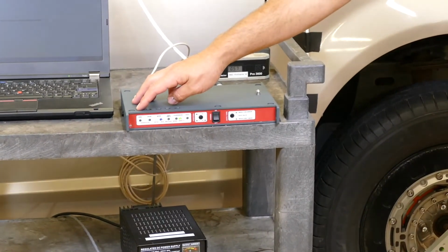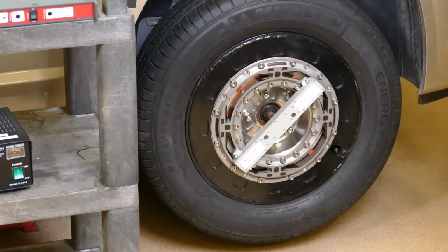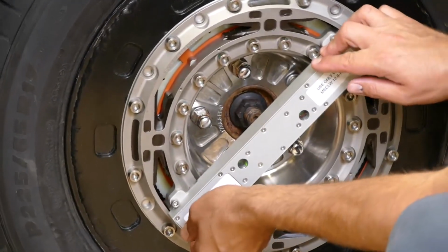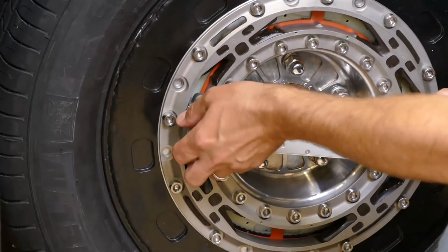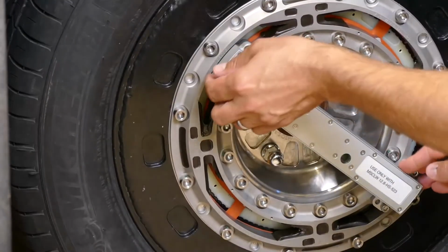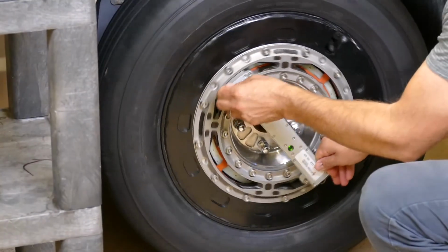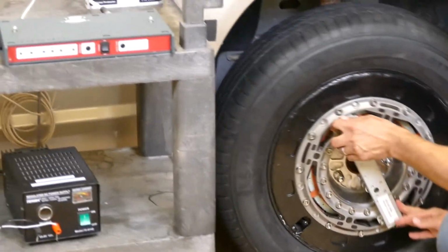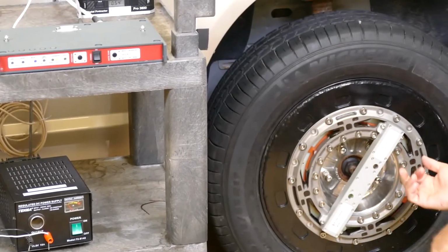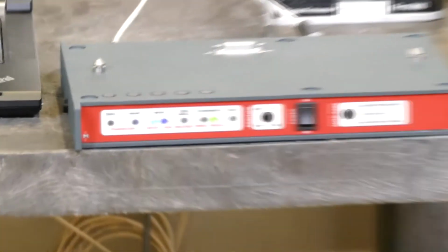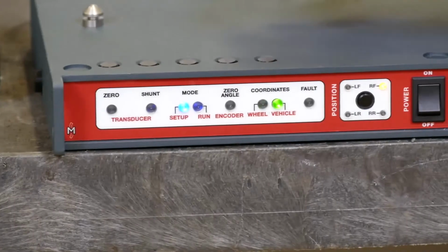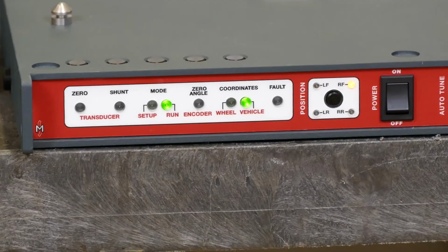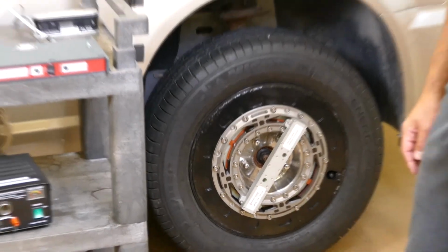Then the third step of the setup is the zero. So we're still in setup mode. We press zero, and we just have to rotate the wheel 2 revolutions. So we're going to press on this telemetry bar, rotate 2 revolutions. Try not to put much load into the transducer. So we passed 2 revolutions, the zero light turned off. So then we can go into run mode, and the transducer is finished with setup and ready to connect to the data acquisition.